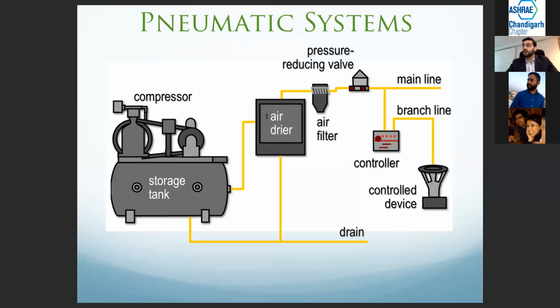Now there's an air dryer in there as well, because if the air that is going through the tubes has a lot of moisture, then we are not going to get the pressure that is required at any given point in the system. So we may be thinking that we're telling the valve to open 100%, whereas the valve may only be open less than that.